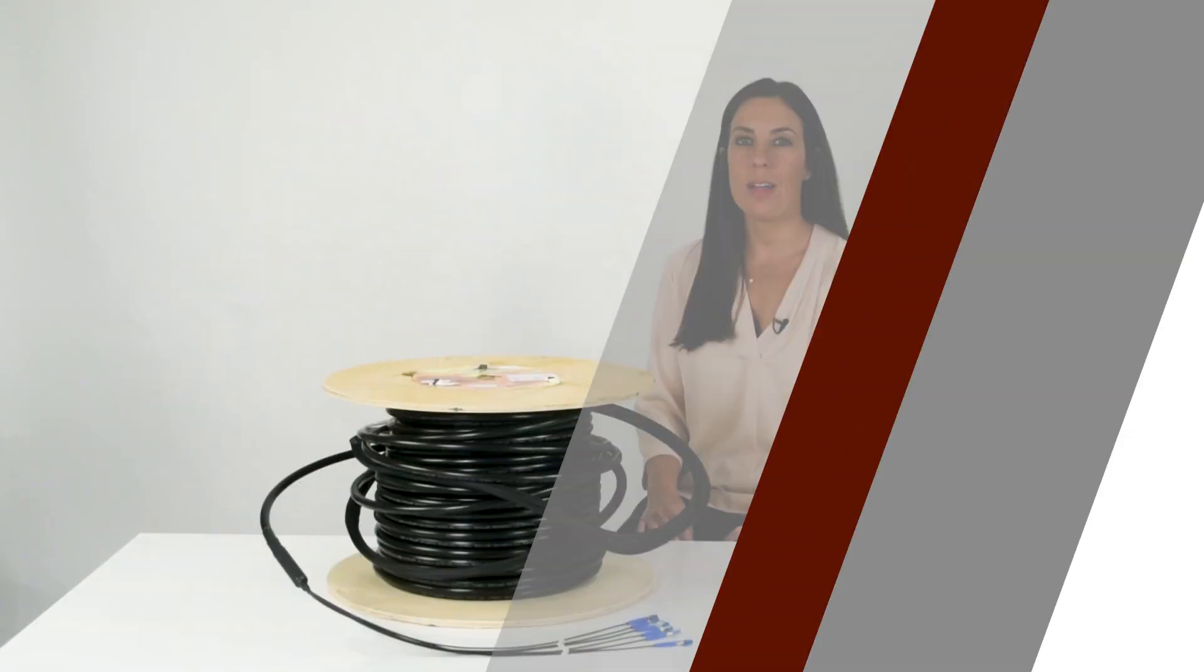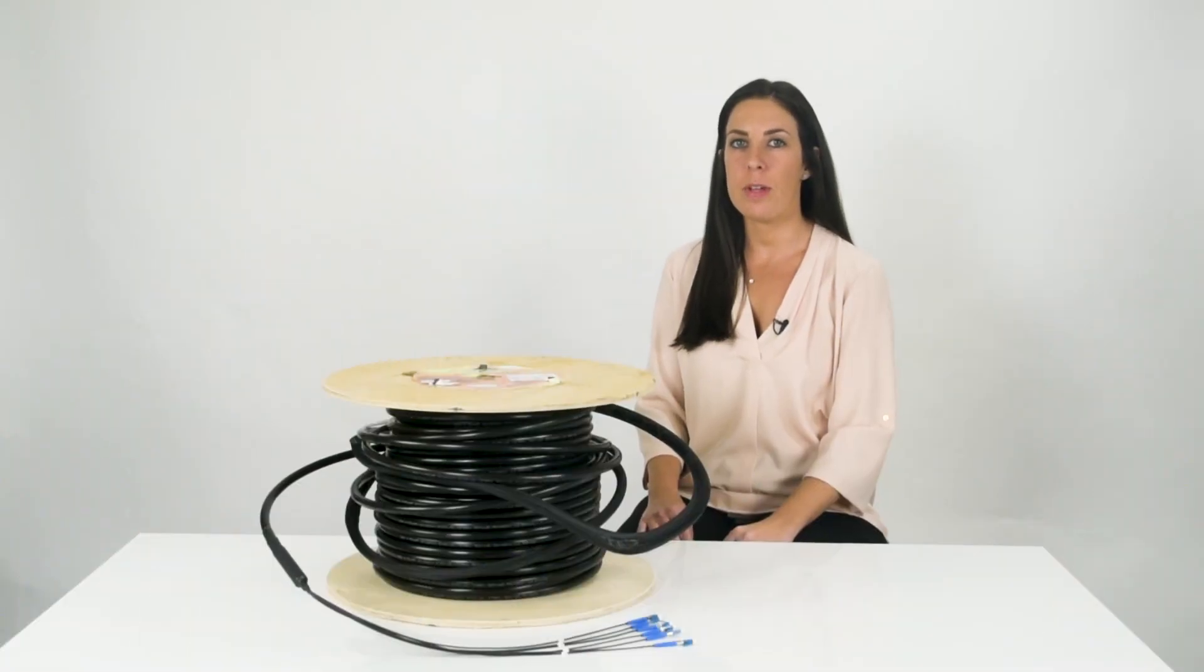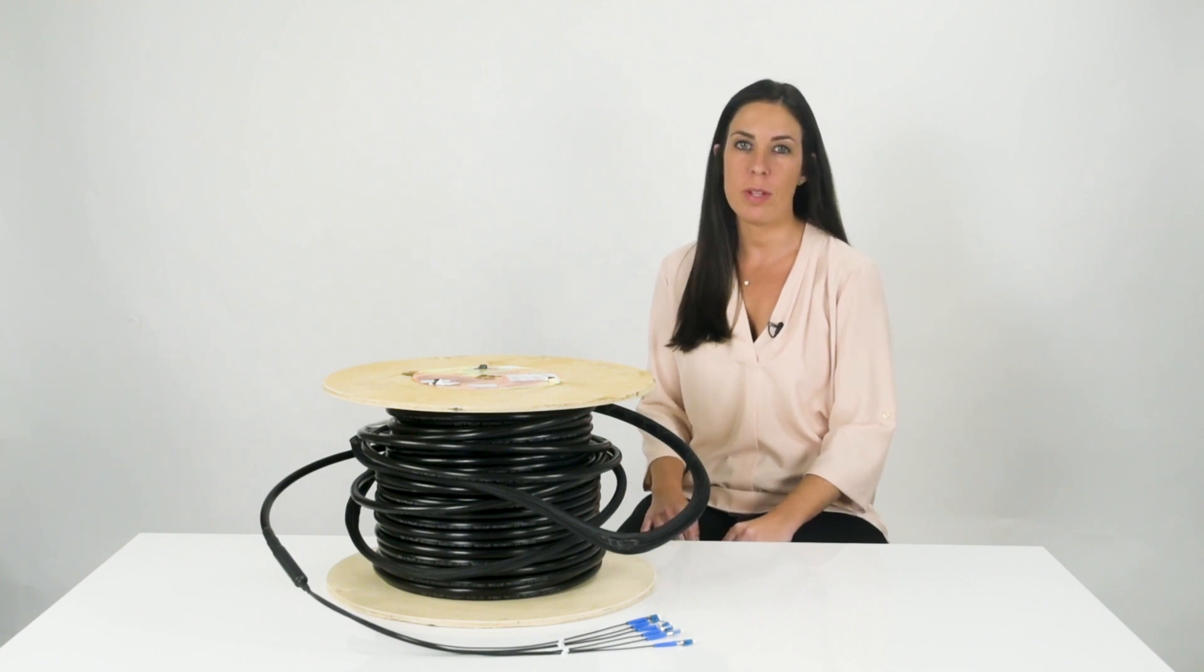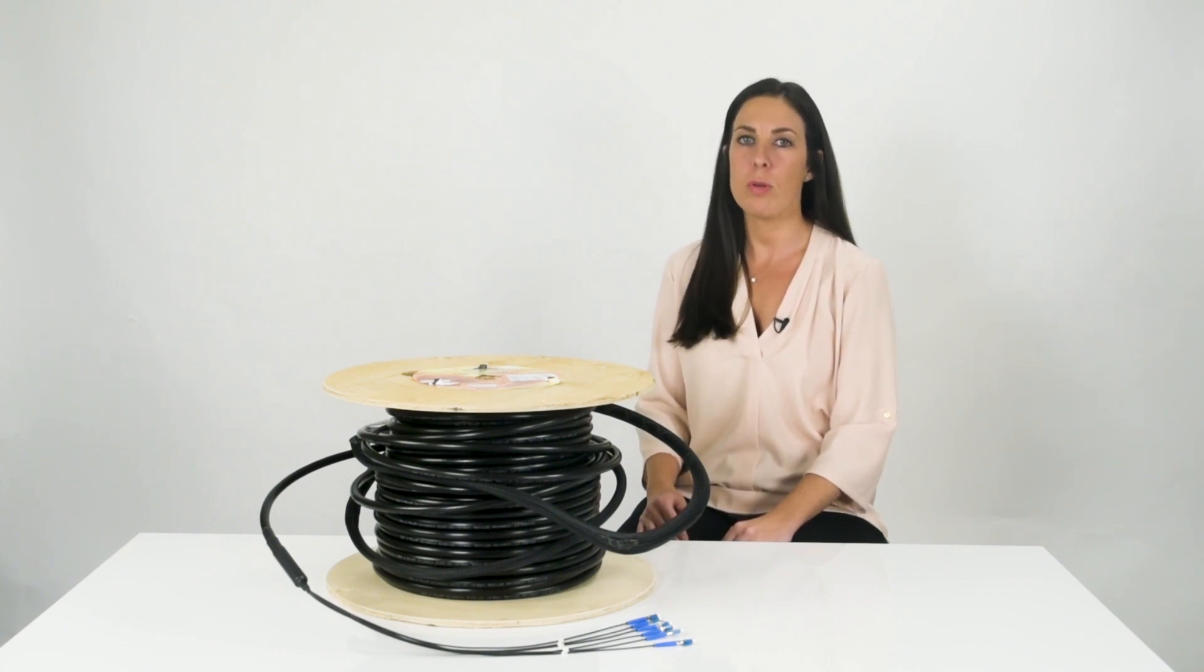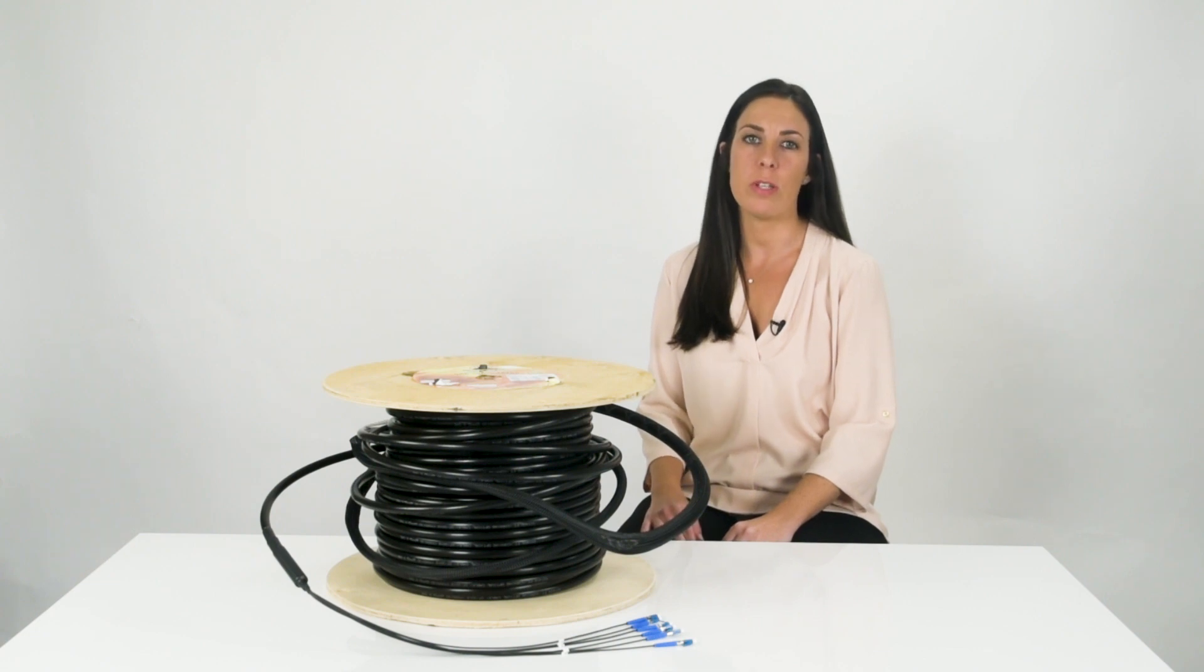One question we get a lot is, is there a specific depth I need to be aware of when directly burying my fiber optic assembly? The depth of fiber cables should be buried is determined by the soil conditions and surface usage. Typically, fiber cables in most areas are installed three to four feet deep.